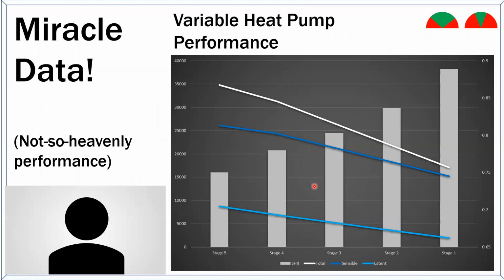Guys, I know systems that by the time they get to about 65% capacity have a latent removal of 0. Well, now you always hear variable speed. They're going to run on low stage, but run longer, and by running longer, it removes more moisture. But not if the evaporator's too warm.